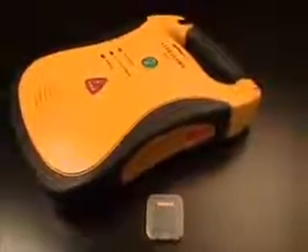The optional data card is used to store extended amounts of ECG data and, optionally, audio data for later review. Note that the Lifeline will store critical ECG data internally even if no data card is installed.